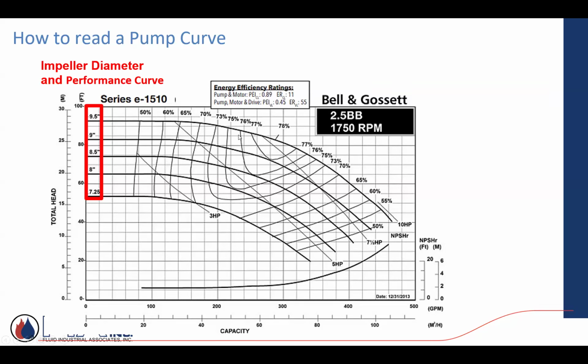Well, where it comes into play is this particular size, this 2.5 BB, can support a full-size wheel, a 9.5-inch diameter impeller, and you can cut it, you can trim it all the way down to 7.25 inches, and anywhere in between, typically in 1/8-inch increments. But you don't want to go below that 7.25. It's not that you couldn't, but that wheel gets so small inside that volute that a very high percentage of the water the impeller is spinning recirculates, and it becomes very inefficient. So this pump curve says, hey, this is the range that you want to operate in terms of selection. If you have something greater or lesser, this isn't a pump for you. Go get a different size, bigger or smaller. So that's the first thing when you look at this pump curve: impeller diameter performance curves.